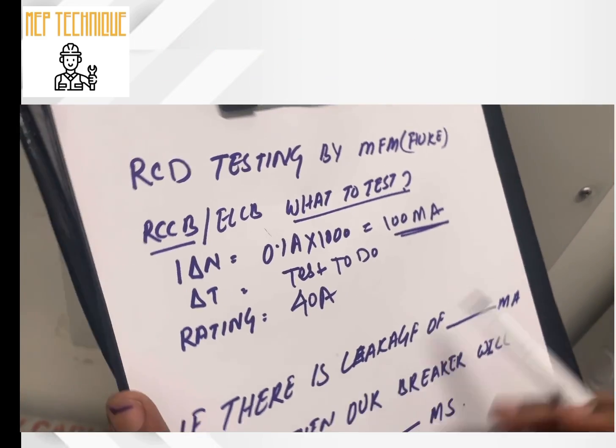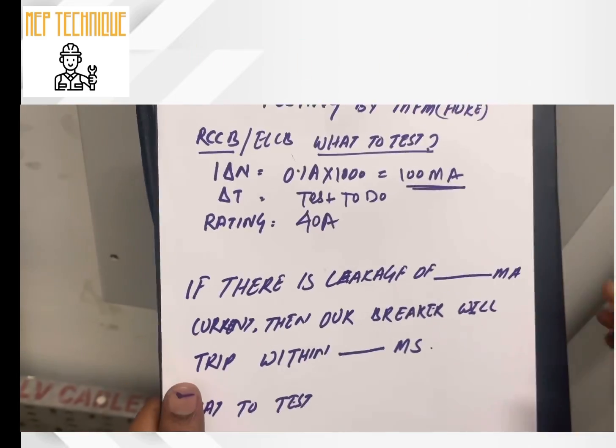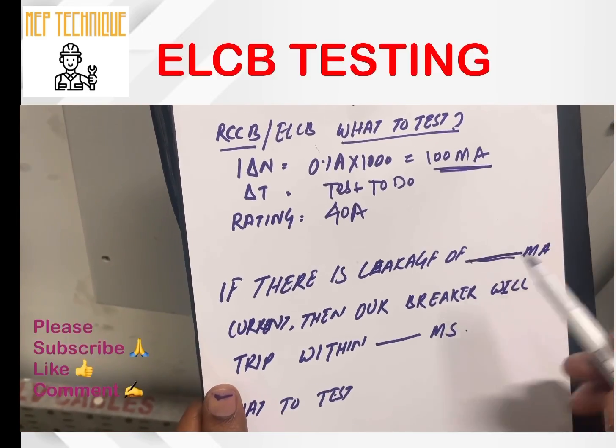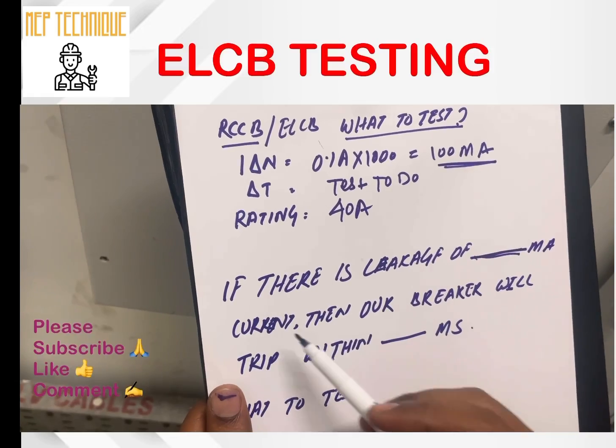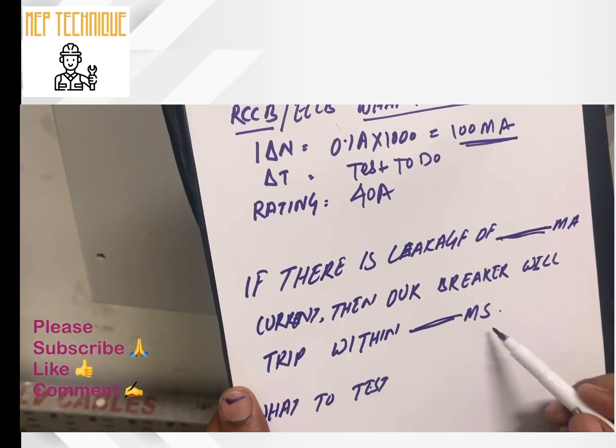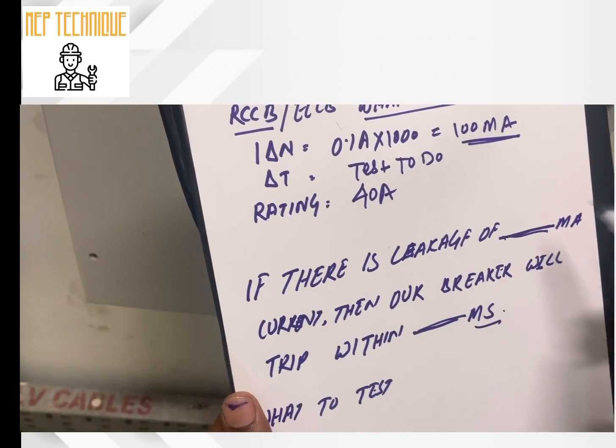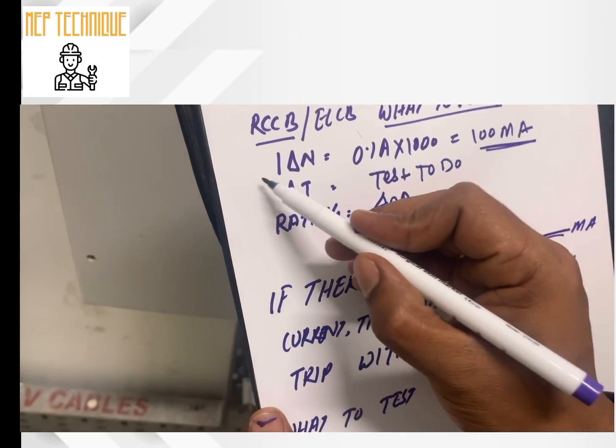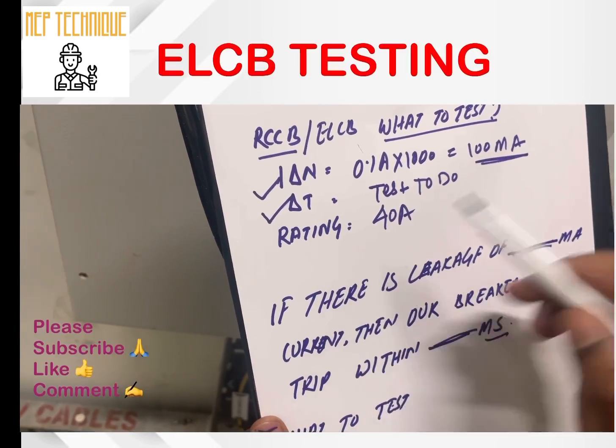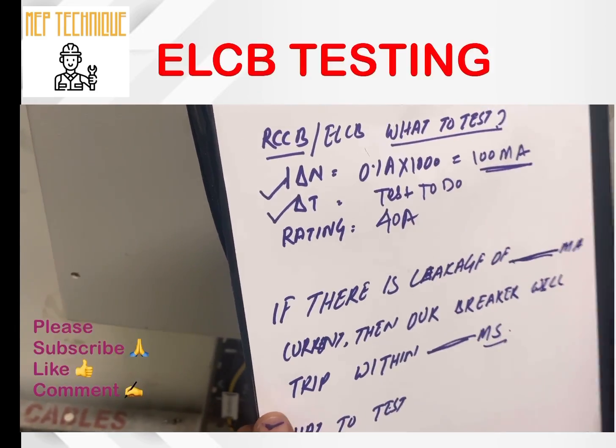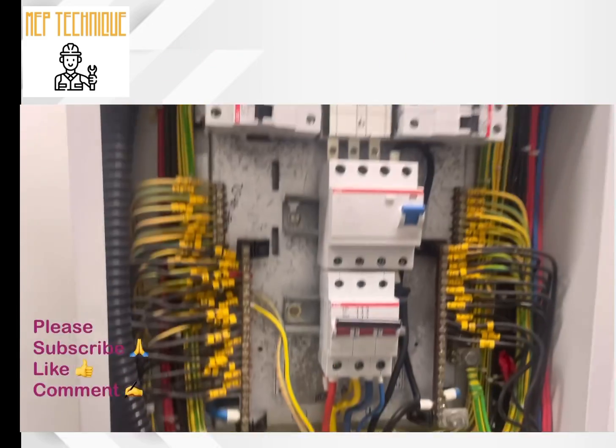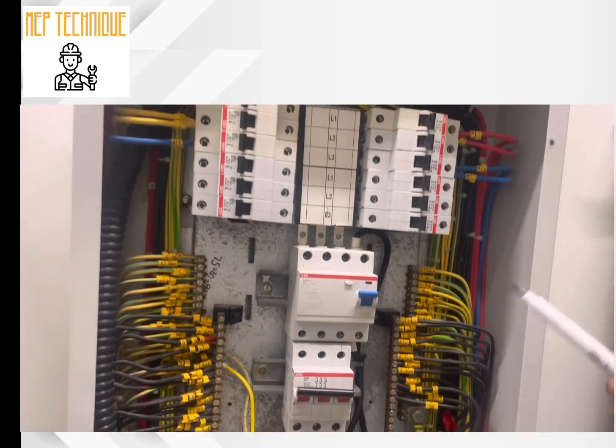Now we are going to check: if there is any earth leakage, within how many milliamperes will the breaker trip, and within how many milliseconds? We are going to check both IΔN and ΔT of the ELCB. The panel is live right now, so we are going to do the test live using this meter.